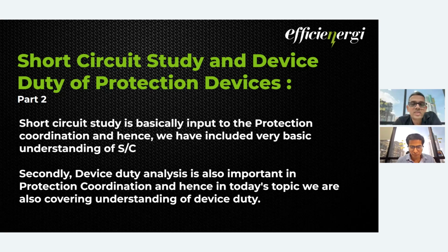Next is your equipment withstand capabilities. Those are very important: your bus bars, your transformers, your cables, your switchgear, and so on. Then, most important for protective device coordination is your coordination selectivity. It all depends on understanding the fault currents with respect to proper trip settings, time delays, etc., and not to mention safety and reliability of the systems, and thus arriving at an optimized device selection and settings.